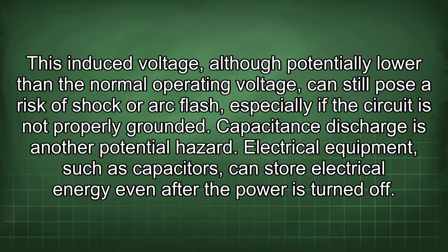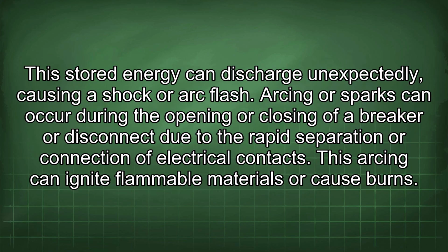Capacitance discharge is another potential hazard. Electrical equipment, such as capacitors, can store electrical energy even after the power is turned off. This stored energy can discharge unexpectedly, causing a shock or arc flash. Arcing or sparks can occur during the opening or closing of a breaker or disconnect due to the rapid separation or connection of electrical contacts. This arcing can ignite flammable materials or cause burns.